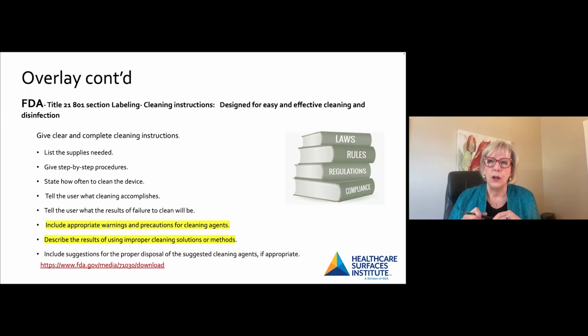When I talk about gaps, we have seen, for instance, an IFU for a warming component for a patient in the operating room, and the recommended cleaning and disinfection was Pine Sol. In a healthcare facility, you cannot use Pine Sol to clean it, but not following the IFU could potentially be a violation for the hospital without going through an entire risk assessment procedure. And we're going to talk more about that. The Institute has found conflict between FDA, infection prevention guidelines in a healthcare facility, and manufacturer's instructions for use. And so there's a gap there that we're working to address.